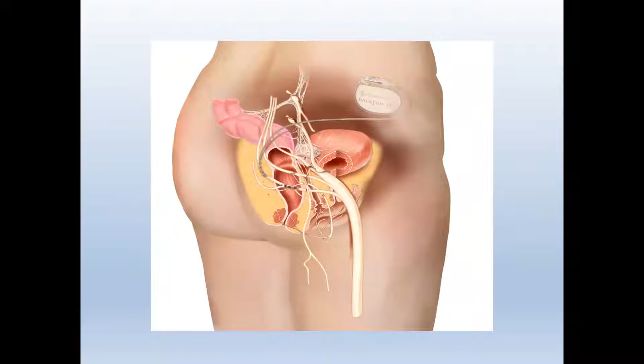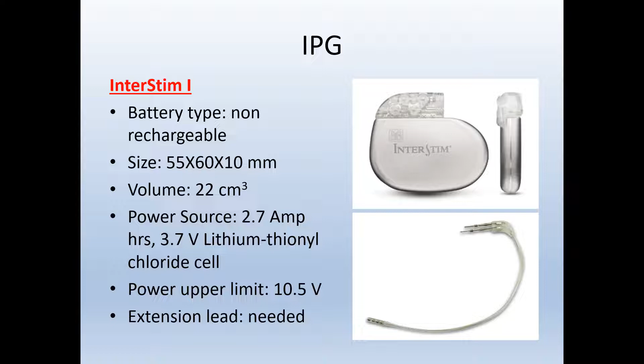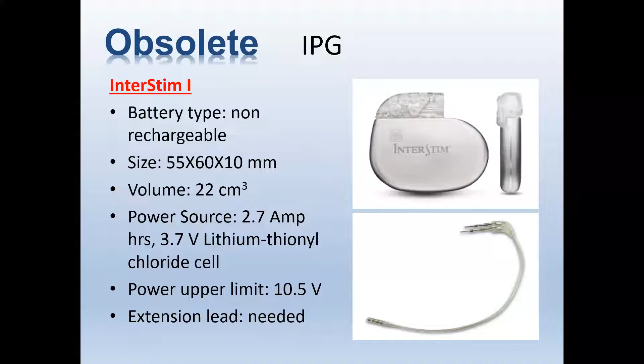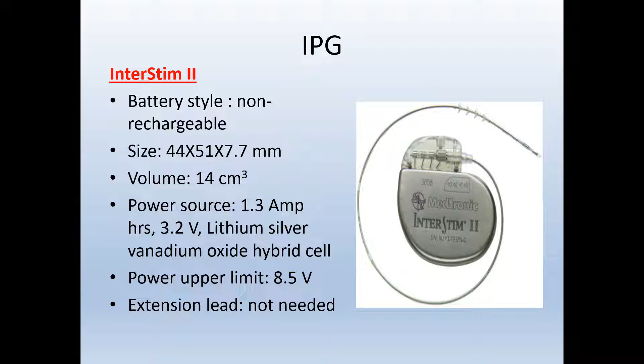Now, the battery itself, the Interstim or the IPG. This is the old Interstim 1, as we see. This is non-rechargeable. It is big. It has a power limit of 10.5 volts. It does have an extension lead. Now, this used to be the norm, but it is now obsolete and not being used anymore, completely replaced by the IPG Interstim 2. Again, it's non-rechargeable and smaller in size, although the power limit is only 8.5 volts, but it doesn't need an extension lead. The battery is connected directly to the tined lead. Also, more technology has emerged for the battery, which I will talk about in a bit.